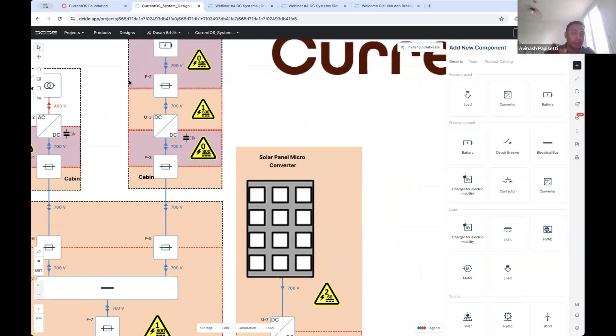Basically, when it says zone 0, it means if you go into that area and touch any metal around it, you know you're going to die. So any unprotected terminals of batteries, even if in string or parallel, are considered zone 0—totally unprotected. In the design, between the converter and before the fuse, we call it zone 0. A battery terminal before the fuse is zone 0. This is the area where you need a different level of know-how to really access it safely.